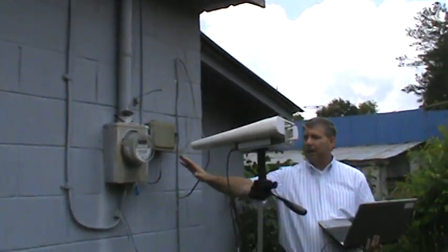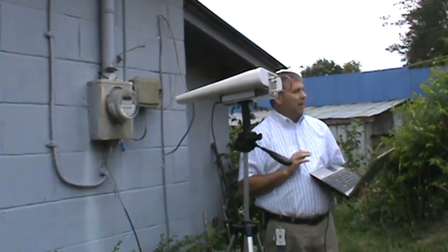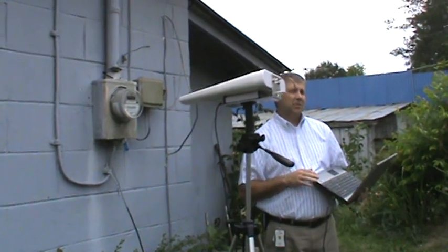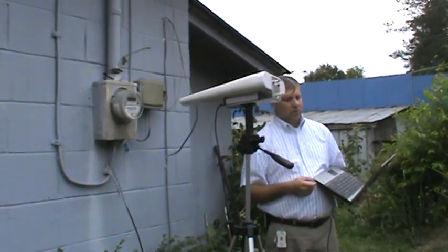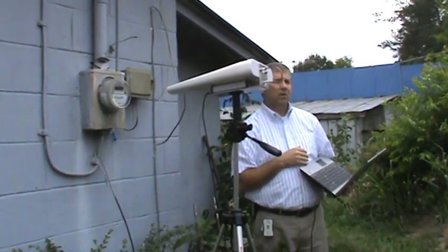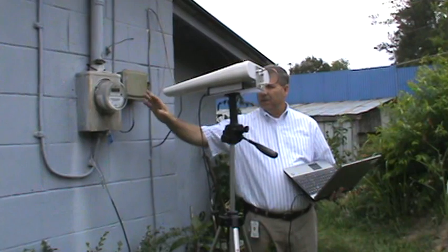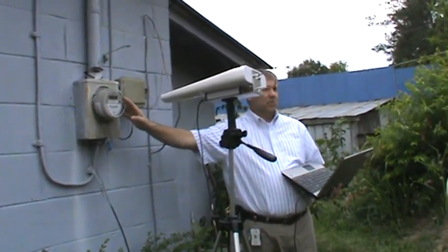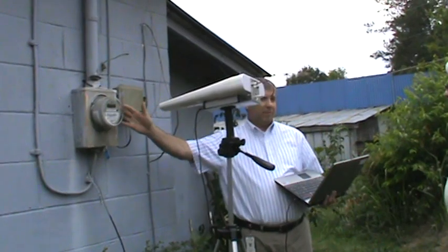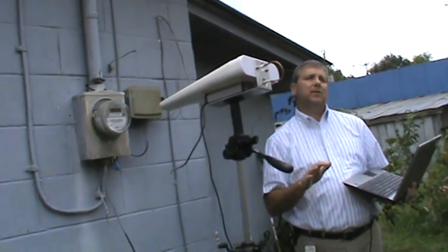Before you do that, let me explain how the meter works. There's a lot of inaccuracies on the internet about AMI systems. There are many different types of AMI systems around the planet, really. Most of what you see on the internet comes from the West Coast. There's a predominantly large number of AMI systems being deployed there called mesh systems. In that particular architecture for a mesh system, every meter is a transmitter. It's also a receiver. And it's also an amplifier. So that meter would talk to this meter would talk to another meter. They all bounce off one another and continuously transmit, which has created a lot of concern. It's still well below FCC limits, but it creates a lot of concern.